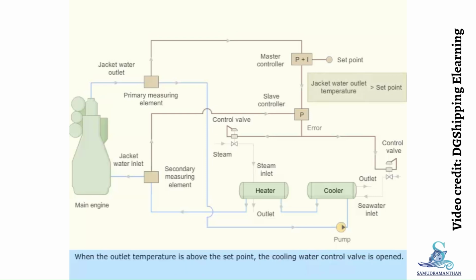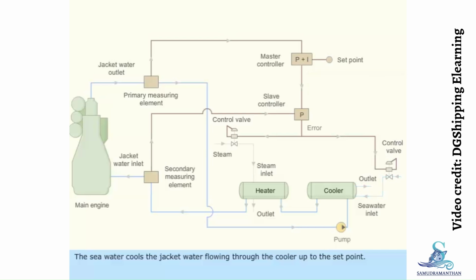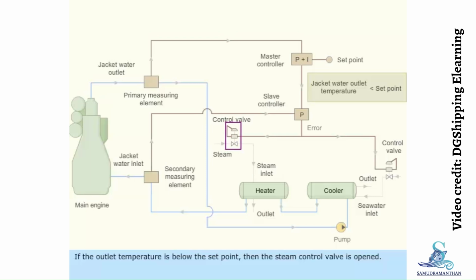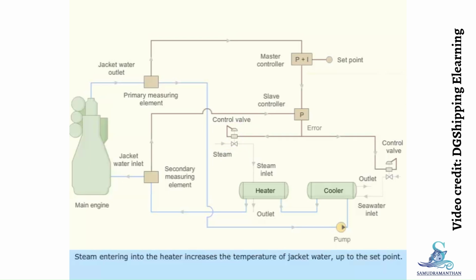When the outlet temperature is above the set point, the cooling water control valve is opened. The seawater cools the jacket water flowing through the cooler up to the set point. If the outlet temperature is below the set point, then the steam control valve is opened. Steam entering into the heater increases the temperature of jacket water up to the set point. In this way, the control system regulates the change in jacket water temperature of the main engine.